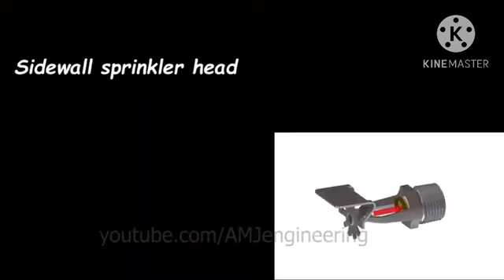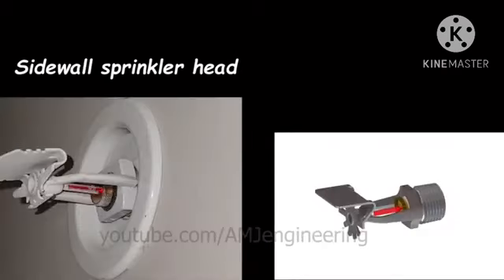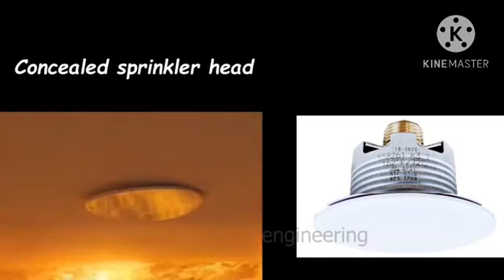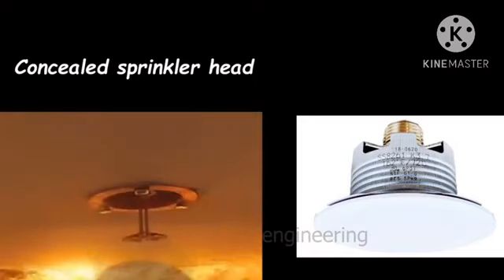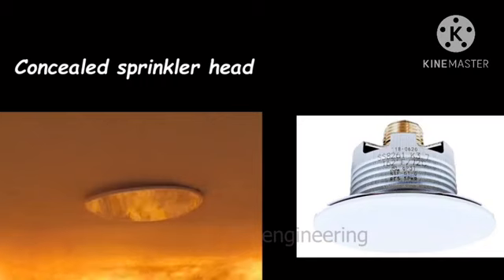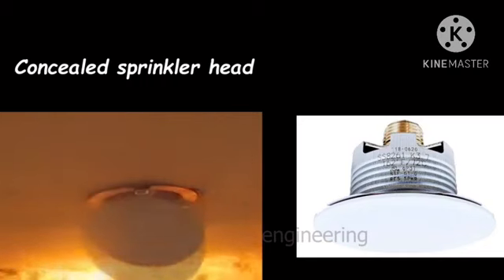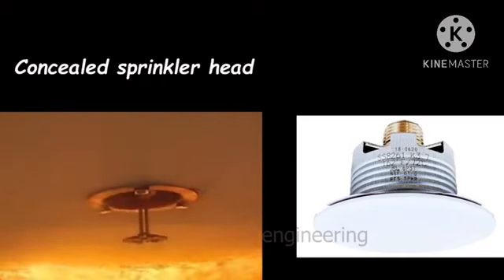Sidewall sprinkler heads protrude horizontally out of the wall, parallel to the floor, rather than descending from the ceiling or being mounted on a pipe pointing upward. Sidewall sprinklers are ideal for small spaces, such as hallways, spaces with obstructions, and where ceiling piping is not available. Concealed sprinkler head. This heat-sensitive plate detaches at temperatures roughly 20 degrees lower than the fire sprinkler head, allowing the concealed sprinkler's deflector to drop and the head to activate.